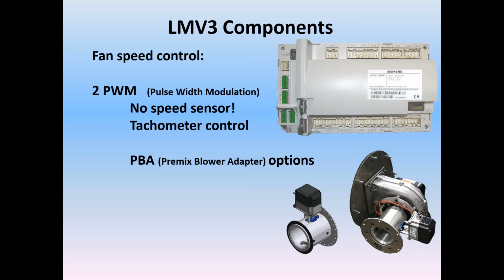You can either control the air with simple PWM signals to the speed of the fan, or the fan speed plus an air actuator, which would be a butterfly in that PBA assembly, and a pipe connection, which would be the fuel inlet there. So you can have fuel, air, and fan speed control on your burner application with a PBA and a PWM option. And we have documentation and support documents to go with it to help you with your application.